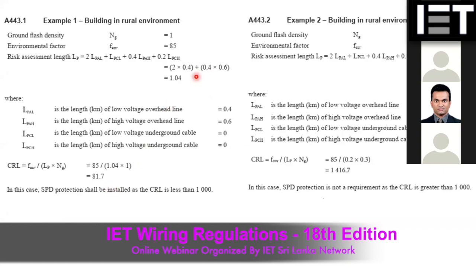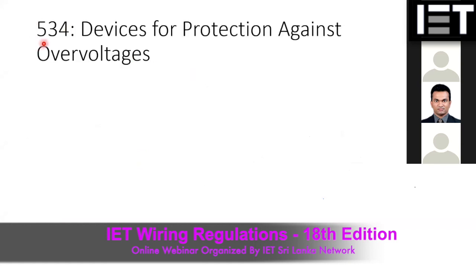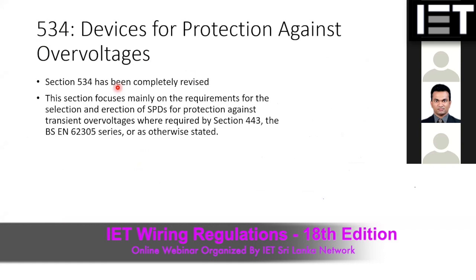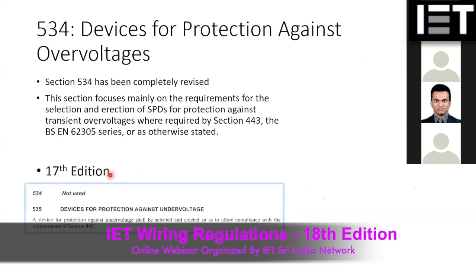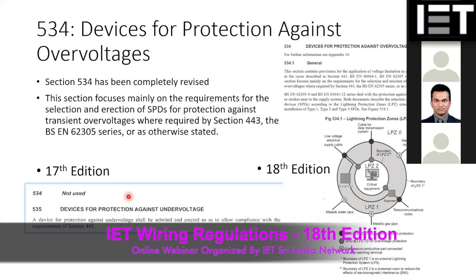This part is a completely new addition, and the surge protective device is also a new addition. That is covered in 534, which is for devices for protection against over voltages. This is also a completely new section added to the new regulation. When you look at the earlier version, the 17th edition, you can see just one sentence, and 534 is not used. It's totally blank. But when you look at the 18th edition, it's a completely new section with several pages of regulation. This is the first page. Likewise, 534 is newly added to protect our installation against transient over voltages.